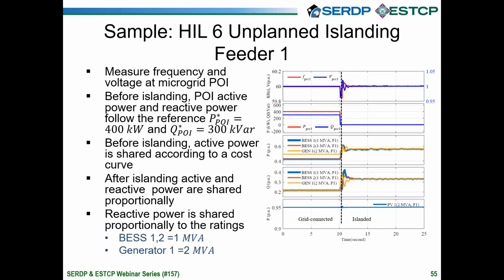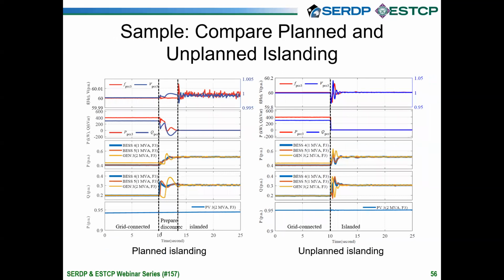The battery and the gensets kick in, and after some transients, they stabilize, as shown, and we are able to remain within the required frequency range, as well as within the rating requirements of the individual DERs that we have on the network. So this is an example of what happens if all of a sudden we have to disconnect, and the algorithm kicks in, and once again after some transient, it stabilizes the microgrid itself.